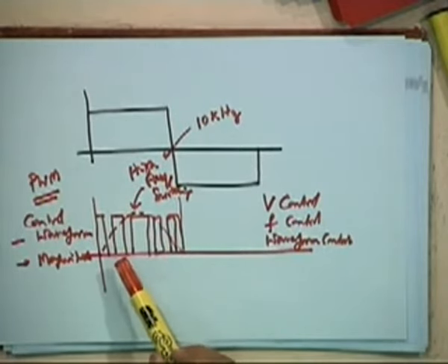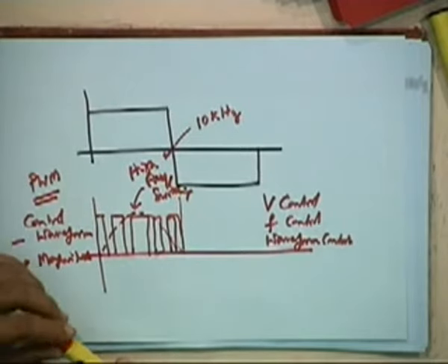Another point which I told you is scalar control or vector control. Scalar control is open loop control. You just control V by F and you control the speed of the motor. But there you don't ensure the angle between the stator and rotor fields; it will assume any angle delta. Vector control or field oriented control is that you push currents into the windings in such a way and at such an instant that the fields are created at quadrature with the rotor fields. That is called field oriented control.